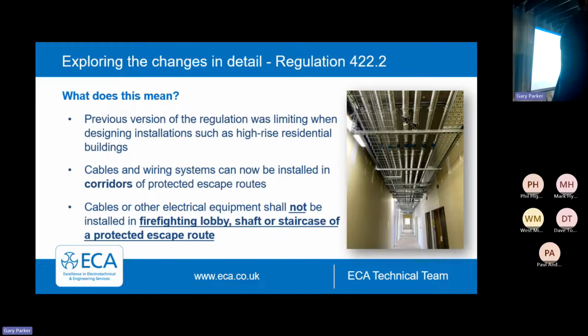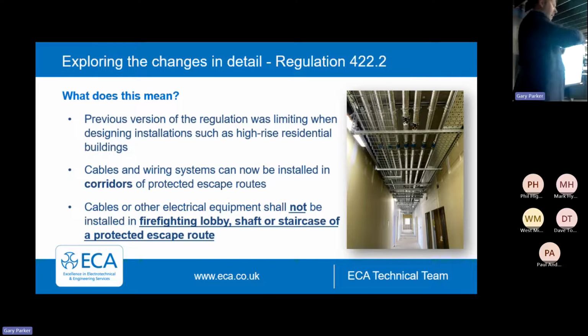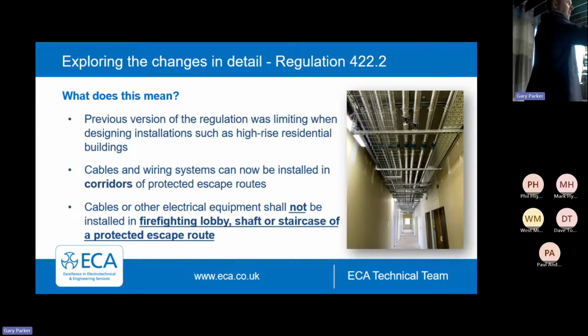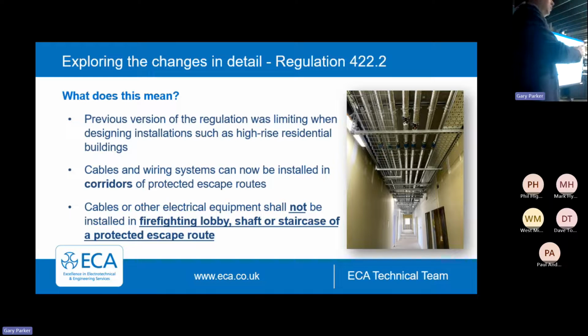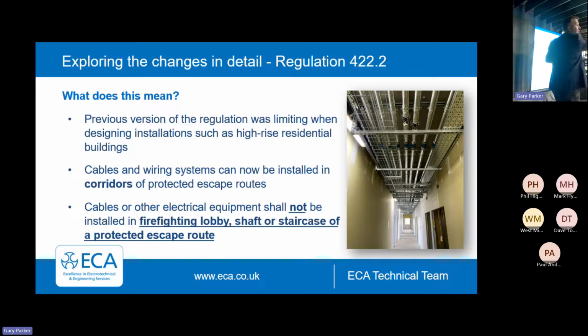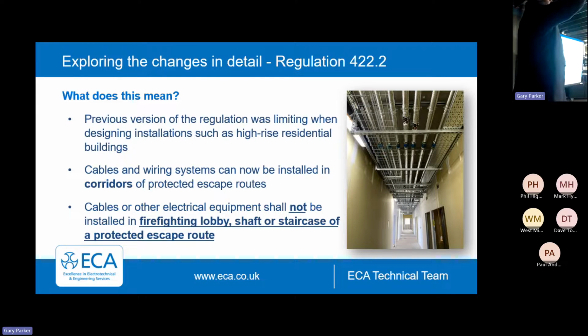Originally it used to talk about cables just through corridors or under doorways. Then they changed it to everywhere, because as a firefighter you're not that bothered about the door - you'll go through a wall, a ceiling, a floor, anything you can get through that you need to get through. So just because that bit of cable over there is protected, this bit isn't - that's probably more of a hindrance, because you're going wherever you want to go in an emergency event. So hopefully it's added some clarity.